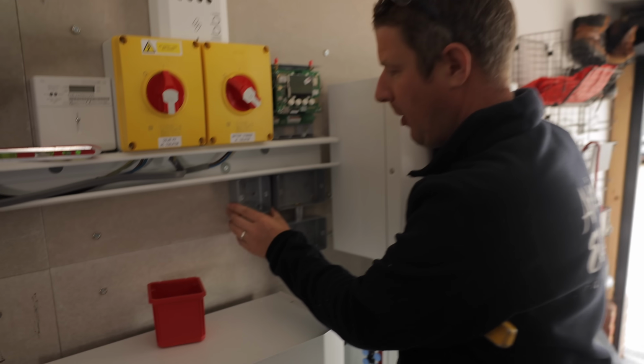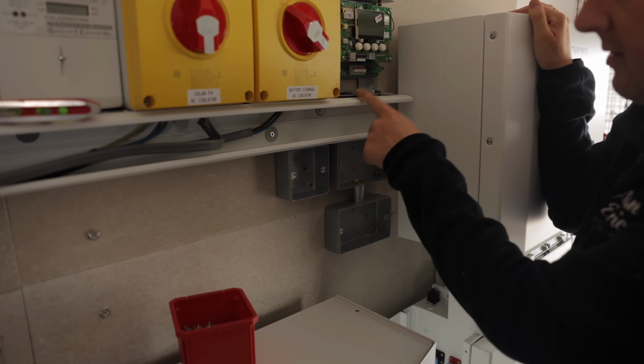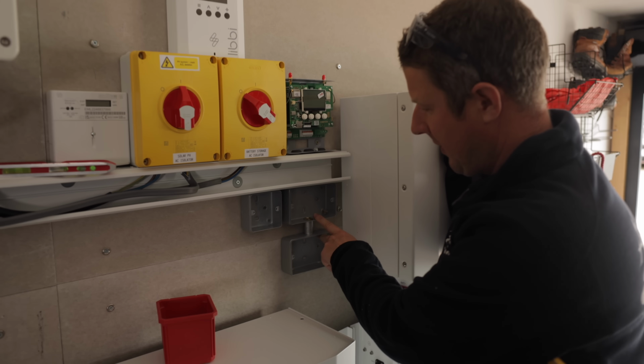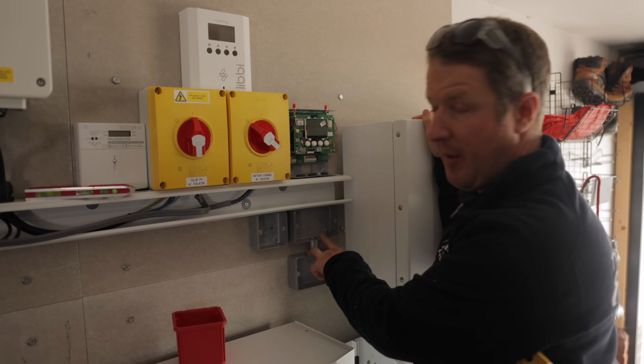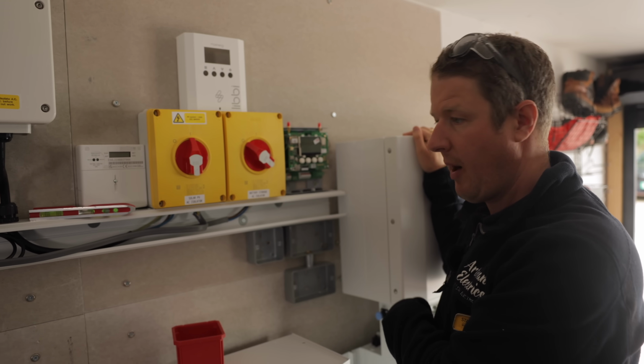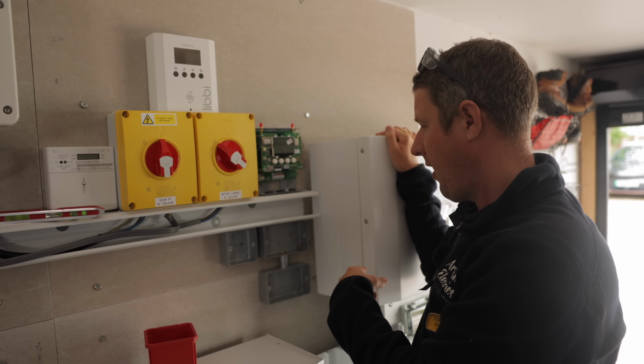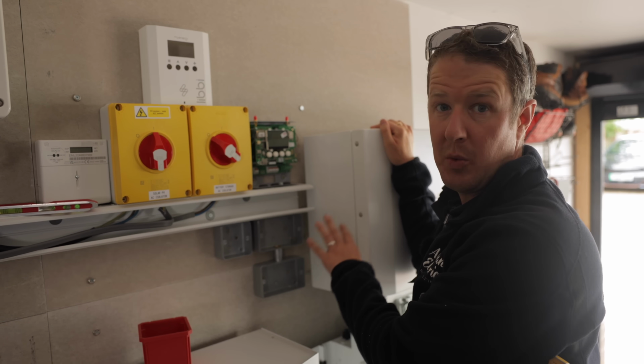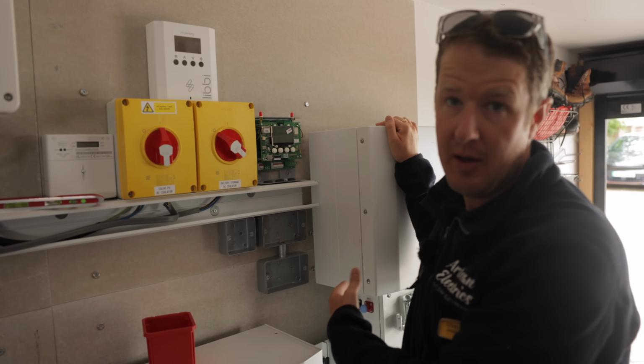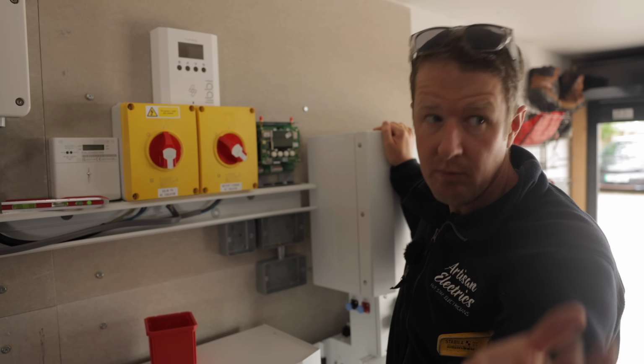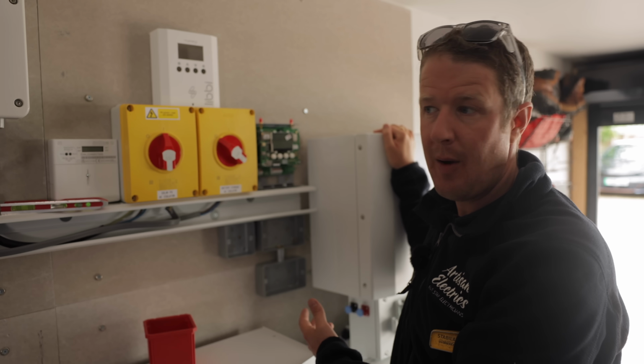So we mounted a back box for our switch fuse connection unit to power the Libbi. Then what we've done is mounted 2 double sockets as well. These are going to be fed from a backup board, which will be running off the Libbi, which will be constantly live, but in the event of a power cut, those 2 sockets will stay live so that the customer's got emergency power just to run a few essential things if they do have a power cut.